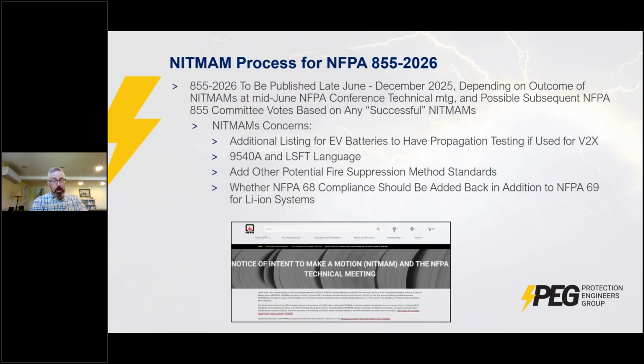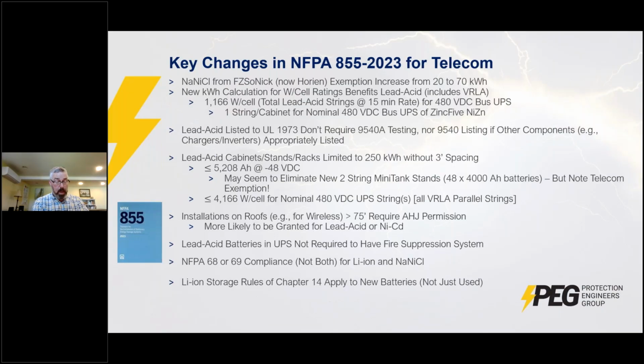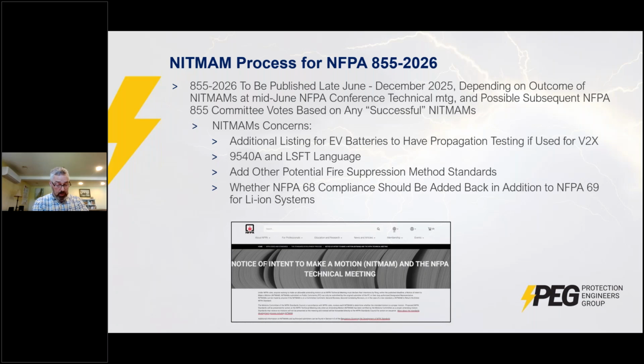In the latest edition, Curtis mentioned the sprinklers. There are also, in earlier editions, options for other types of suppression systems, but some of those have been struck out. There's generally a feeling that some of these newer systems or hybrid systems, maybe clean agents and others, don't work as effectively on lithium fires, so they were removed as options. But there are folks who, maybe rightly so, say the standard's not just about lithium. These could have been fine for lead acid or other applications. They should be put back in. So they're going to argue that some of those removed suppression technologies should be put back in. That seems like maybe a reasonable request. There's an amending motion to put back in the need to have both NFPA 68 and 69 as explosion protection measures. There's a request to push.